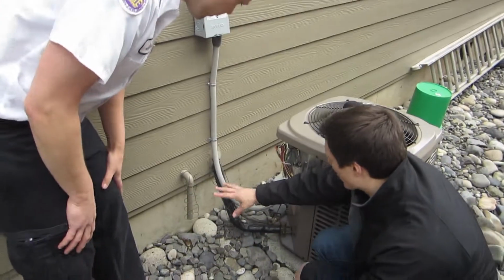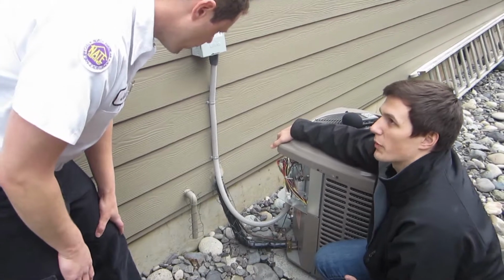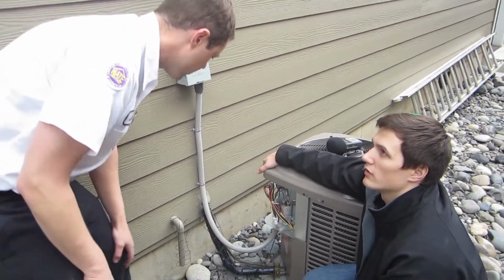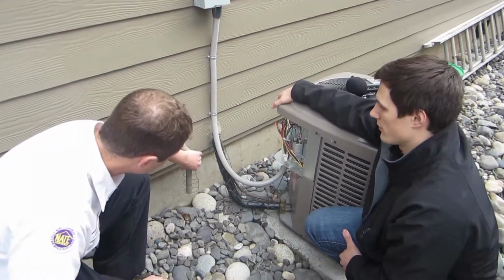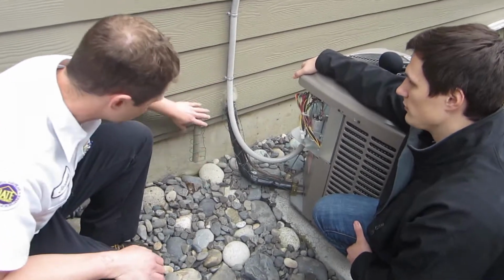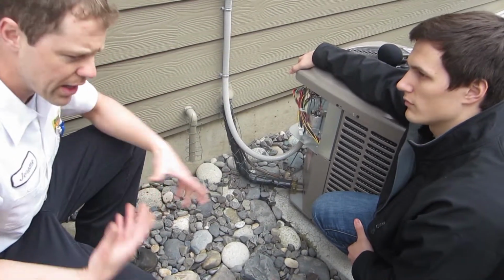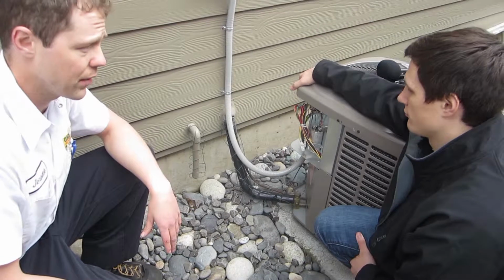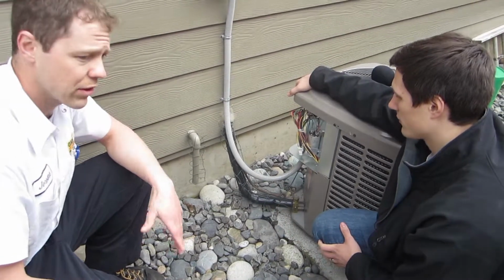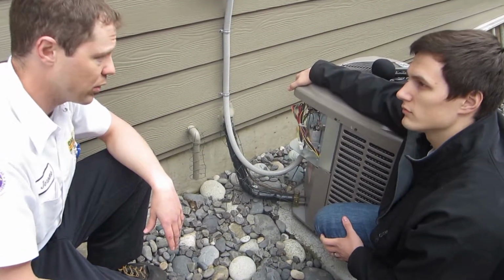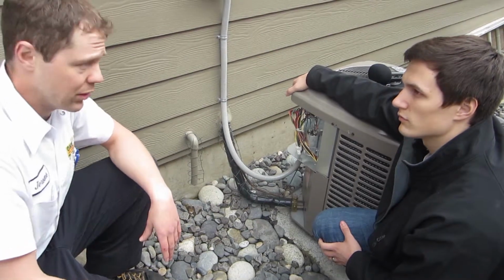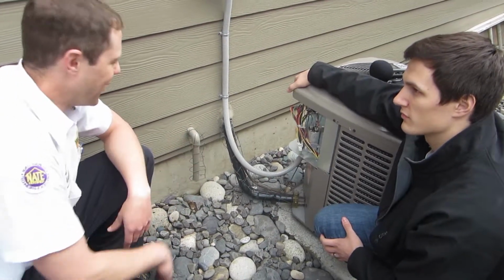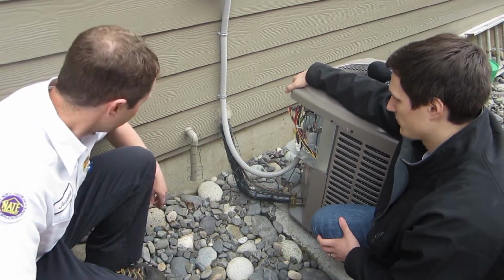What about this guy? We got some wiring on here. Is that okay? What's the purpose of that for? Well, the homeowner, Max here, put some protective wiring around the line set here and then the drain. And it was to try to deter his dog from chewing this stuff up. All right, that's fine. No big deal. And that's actually somewhat of a common problem. Sometimes dogs, for some reason, are attracted to the noise these things produce, and they'll chomp on the refrigerant lines, and they can do some damage.